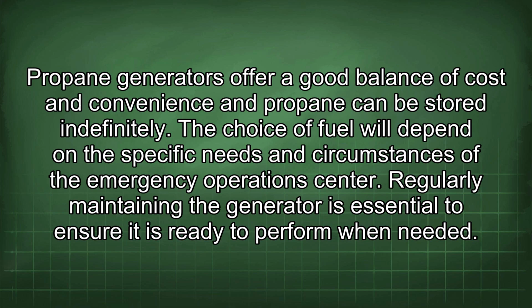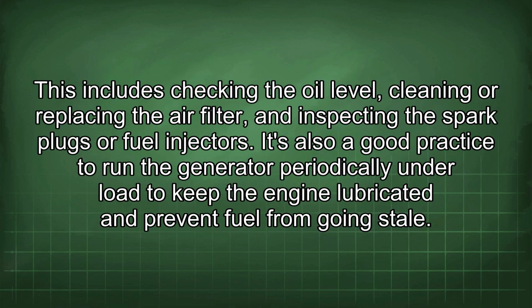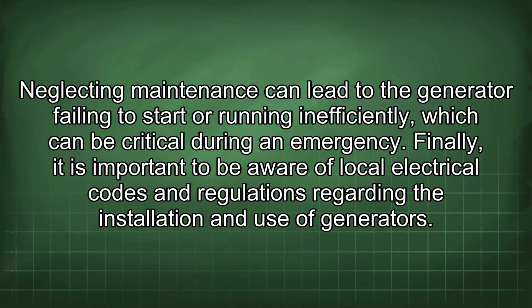Regularly maintaining the generator is essential to ensure it is ready to perform when needed. This includes checking the oil level, cleaning or replacing the air filter, and inspecting the spark plugs or fuel injectors. It's also a good practice to run the generator periodically under load to keep the engine lubricated and prevent fuel from going stale. Neglecting maintenance can lead to the generator failing to start or running inefficiently, which can be critical during an emergency.